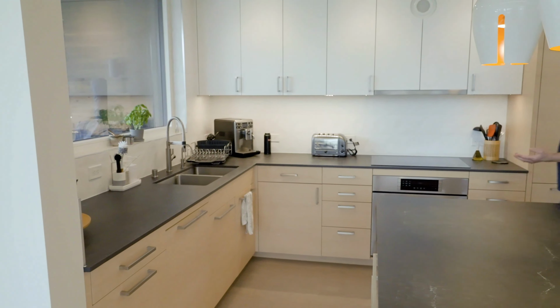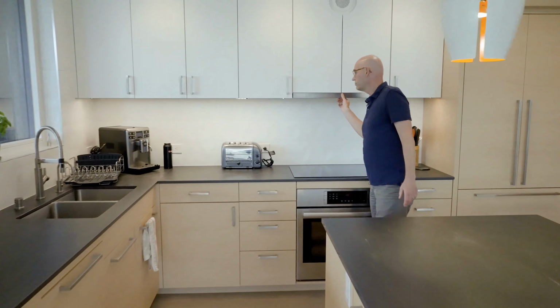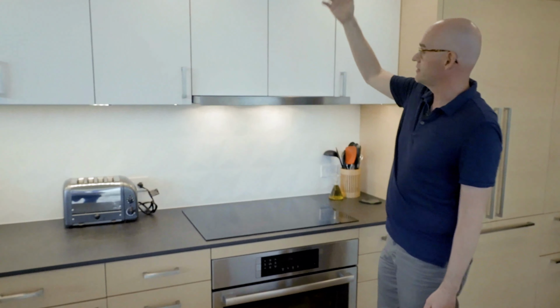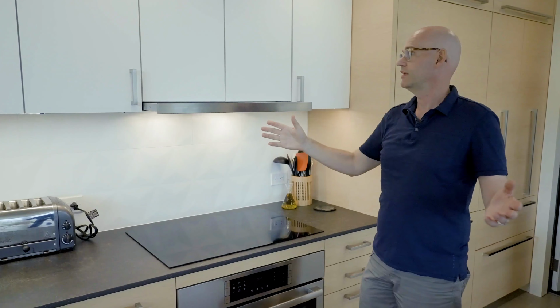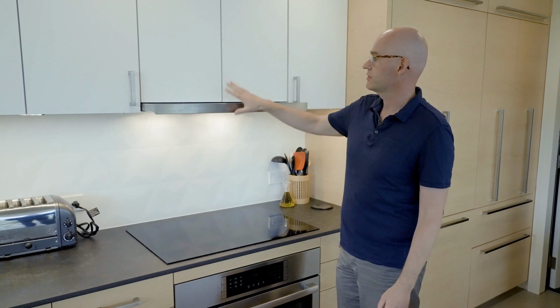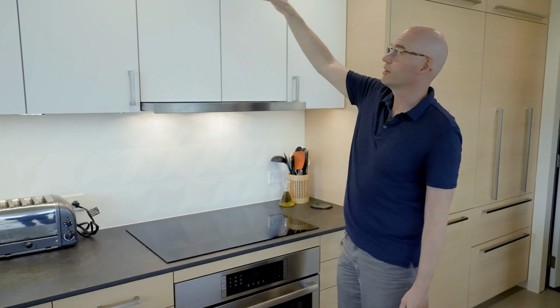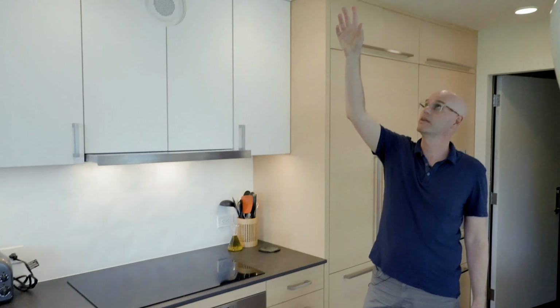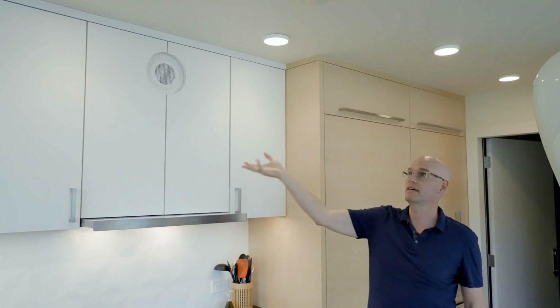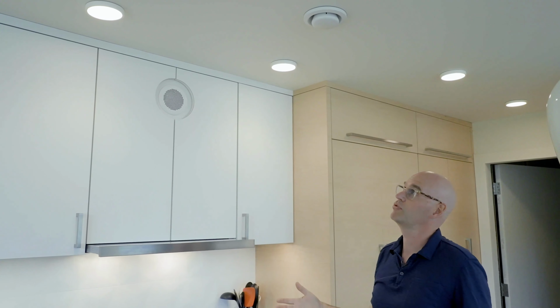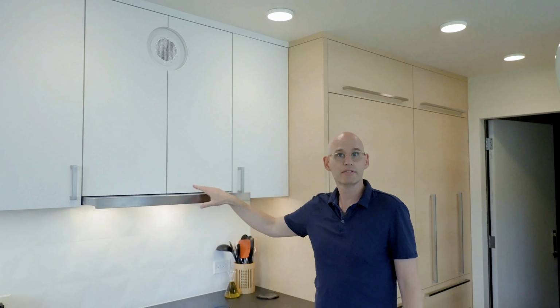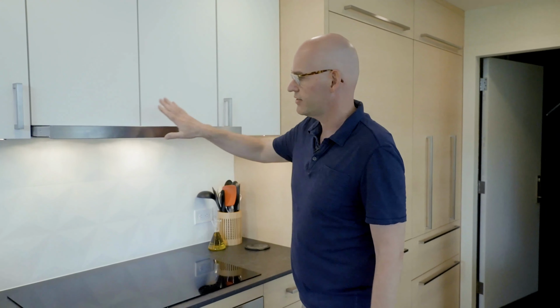So one of the features of our house is a very basic range hood that simply pulls out and recirculates the air. Because we have a whole house ventilation system, we don't exhaust the air from cooking. We bring it back in here, and our whole house ventilation system, which is located right above me, actually is the machine that takes the air to the outside. And we do that because the whole house system has a heat recovery in the actual ventilator, whereas a range hood would not. And also a passive house is an airtight building, so if we had a device that simply sucked on it, it wouldn't work because there's no opportunity for that air to be replaced. So that's a unique feature.